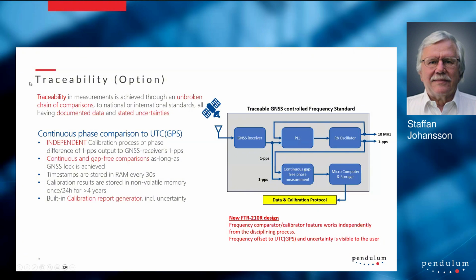Traceability is an option which is software enabled via a license. And that is a very important property of this unit. Traceability in measurements per definition is achieved through an unbroken chain of comparisons to national or international standards, all having documented data and stated uncertainties. And we achieve that via this continuous phase comparison to the satellite UTC of the GPS system.